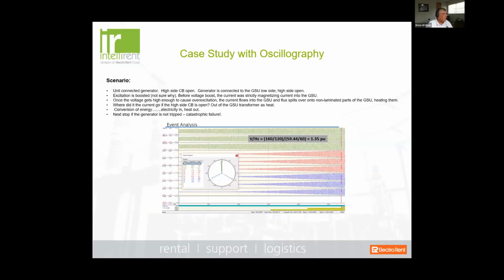So if we look here, we can see a unit-connected generator with the high side circuit breaker open, connected to the GSU on the low side. There was a big boost in excitation, and I'm not exactly sure why, but it was probably caused by the static exciter, where we see a very high amount of current flowing through and the flux spilling over. That flux spillover causes excessive heating, especially in the non-laminated components. This is where you're going to have a problem. If we don't trip that generator offline, we're certainly going to see a catastrophic failure.